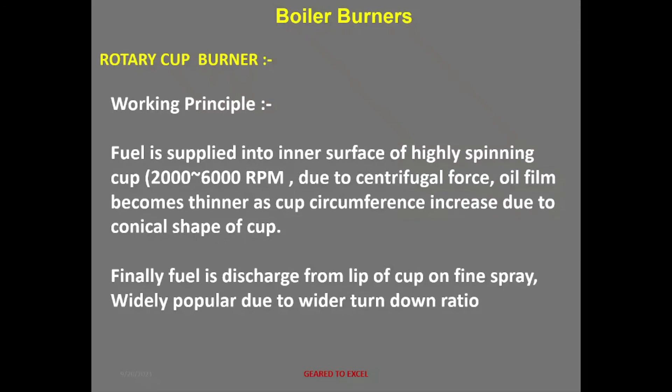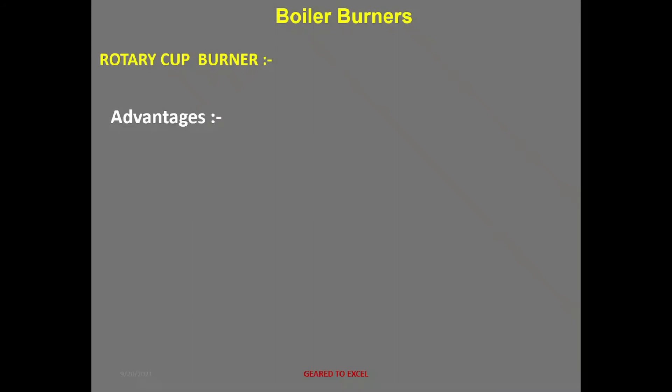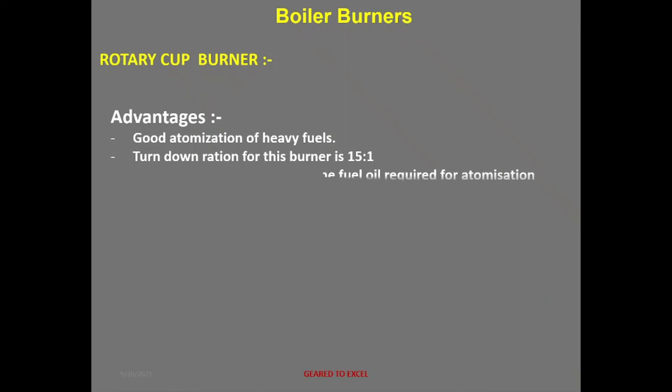Rotary cup burner advantages and disadvantages. Advantages: good atomization of heavy fuels; turndown ratio of 15:1; low preheat temperature of fuel oil required for atomization; no high-pressure fuel in the line. Disadvantages: complex in construction and costly to maintain.